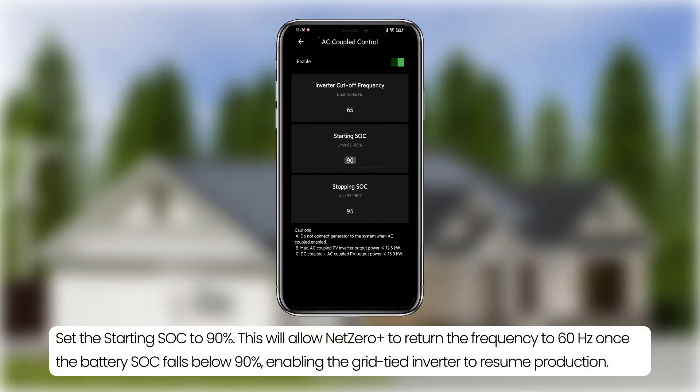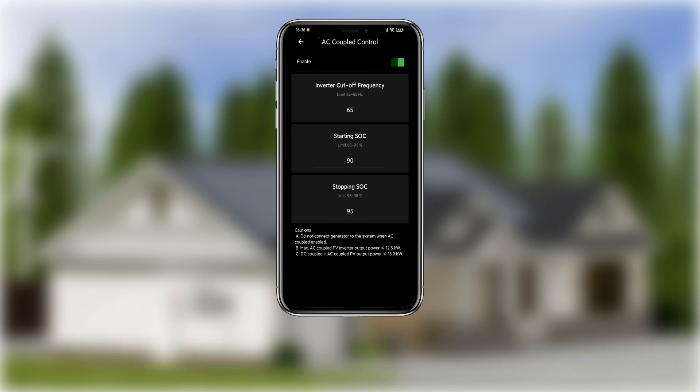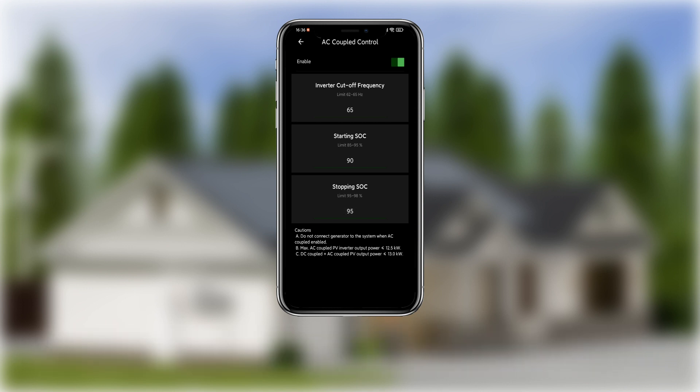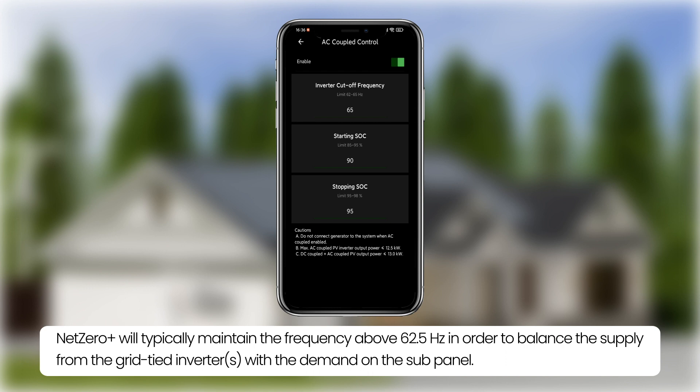Set the starting SOC to 90%. This will allow Net Zero Plus to return the frequency to 60 Hz once the battery SOC falls below 90%, enabling the grid-tied inverter to resume production. Set the stopping SOC to 95%. This will allow Net Zero Plus to automatically adjust the frequency to reduce the output of the grid-tied PV inverter once the battery reaches 95% or more. Net Zero Plus will typically maintain the frequency above 62.5 Hz in order to balance the supply from the grid-tied inverters with the demand on the sub-panel.